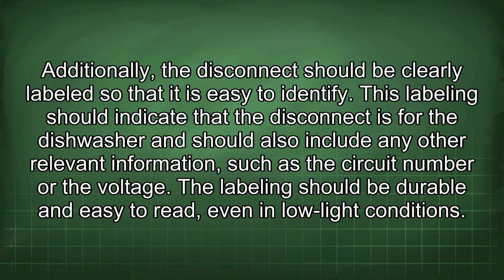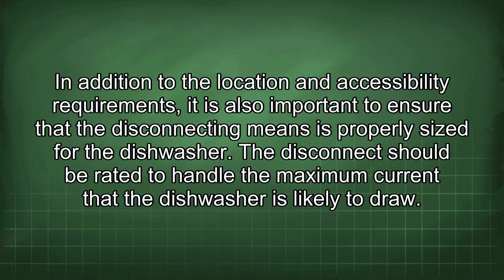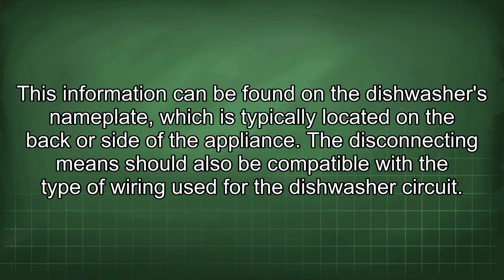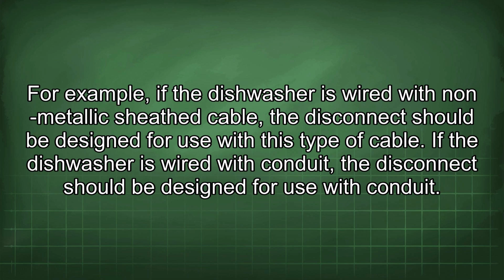This labeling should indicate that the disconnect is for the dishwasher and should also include any other relevant information, such as the circuit number or the voltage. The labeling should be durable and easy to read even in low light conditions. In addition to the location and accessibility requirements, it is also important to ensure that the disconnecting means is properly sized for the dishwasher. The disconnect should be rated to handle the maximum current that the dishwasher is likely to draw. This information can be found on the dishwasher's nameplate, which is typically located on the back or side of the appliance. The disconnecting means should also be compatible with the type of wiring used for the dishwasher circuit. For example, if the dishwasher is wired with non-metallic sheath cable, the disconnect should be designed for use with this type of cable. If the dishwasher is wired with conduit, the disconnect should be designed for use with conduit.